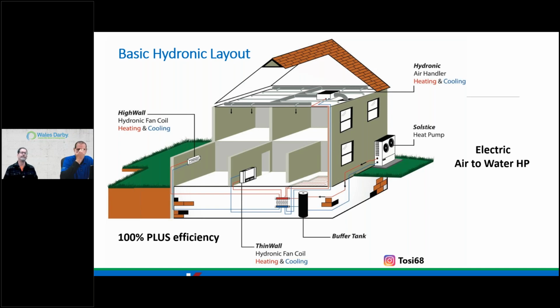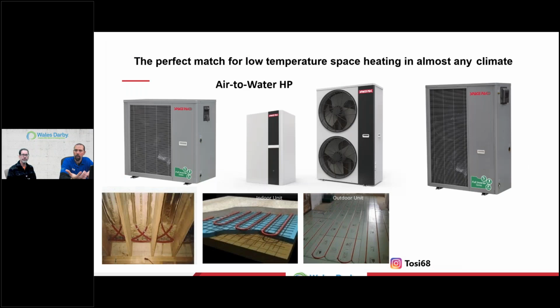Just going back to that buffer tank, one of the comments was about sizing them. I don't know if you're going to go in depth with that, but we go over that in the SpacePak air to water webinars we've done. What's nice about the newer inverter air to water heat pumps is that, because of their turn down, it gives us a better ability to go with a smaller buffer tank.